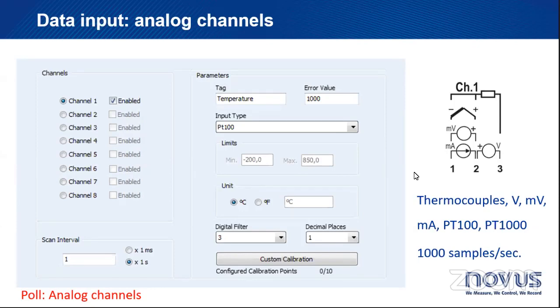So one example that I'll give you is measuring temperature with a type K thermocouple. And this thermocouple has a very fast answer, okay? So very quickly it will respond to any temperature changes. Well, do you want to see temperature fluctuating every millisecond on one decimal place? I would guess you don't want to see that in most cases. In some cases, you might want to see that. So in that case, what you do is you apply a digital filter that by default is 3, but it's configurable from 1 to 5. By default, you put a filter so you don't see that temperature fluctuating that much.